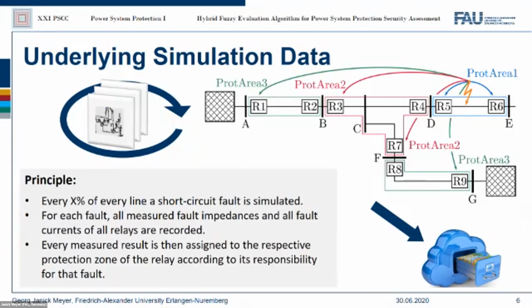Traditional approaches use the resistance and reactance of the connected equipment as reference data to calculate the individual setting for each relay. But as already explained, various effects are influencing the measurement results. So in order to take all possible eventualities into account, a systematic fault analysis is done in advance to generate realistic and reliable reference data based on simulations. Depending on the required attention to detail, a short circuit fault simulation is carried out at every X% of every line of the grid. For each individual simulated fault, all measured fault impedances and all fault currents of all relays are recorded. The measurement result of each relay is then assigned to the respective protection area of the relay according to the responsibility for the fault.